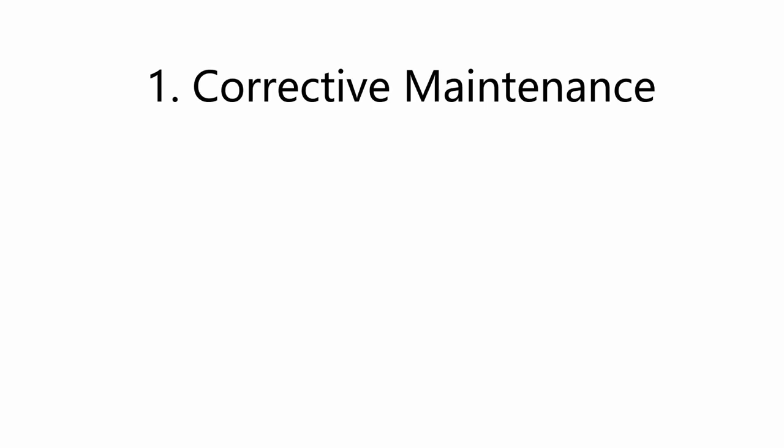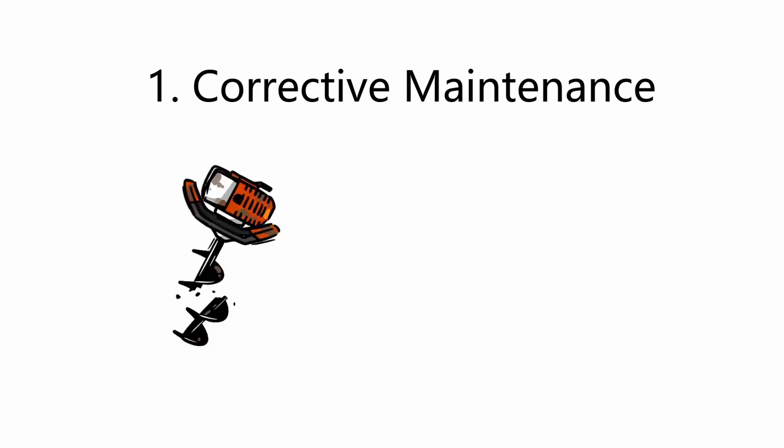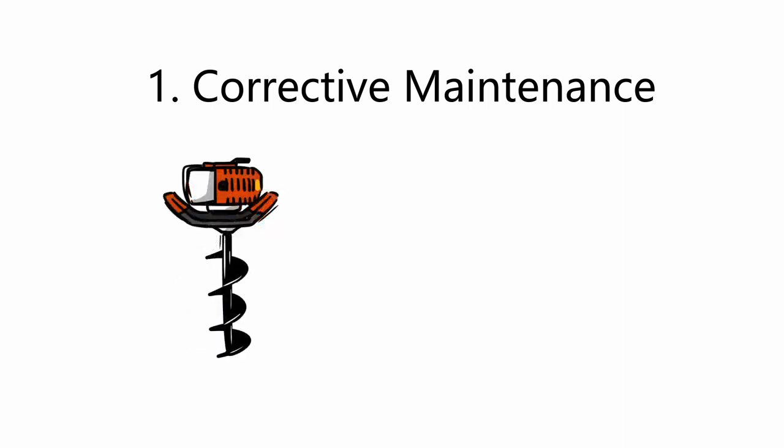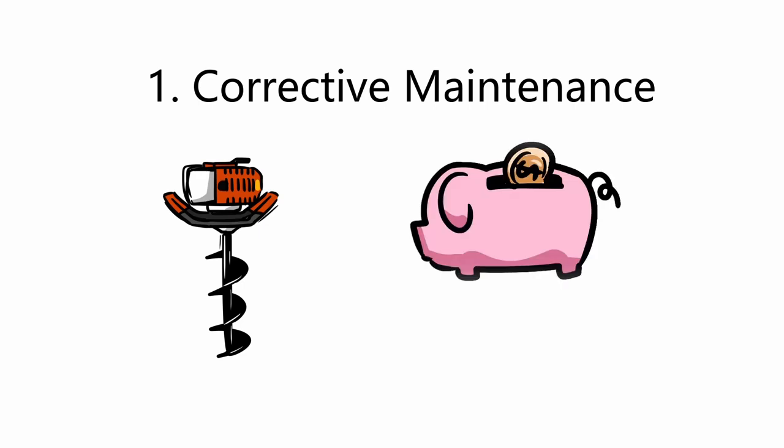1. Corrective maintenance. Maintenance is carried out following detection of an anomaly and aimed at restoring normal operating conditions. This approach is based on the firm belief that the costs sustained for downtime and repair in case of fault are lower than the investment required for a maintenance program. This strategy may be cost-effective until catastrophic faults occur.